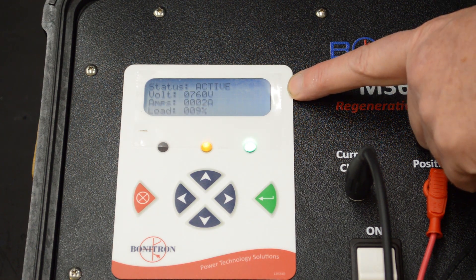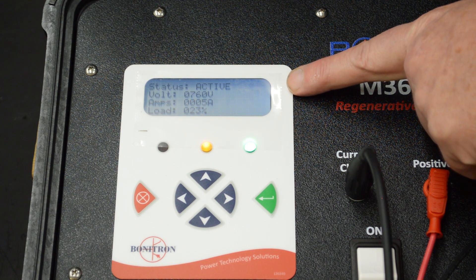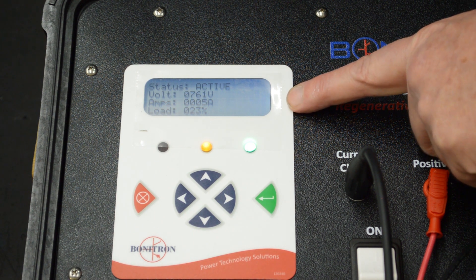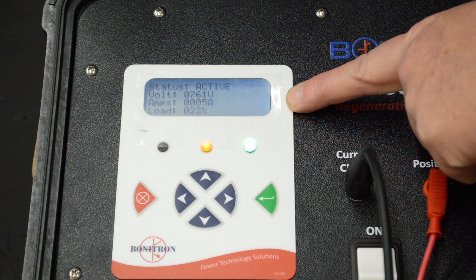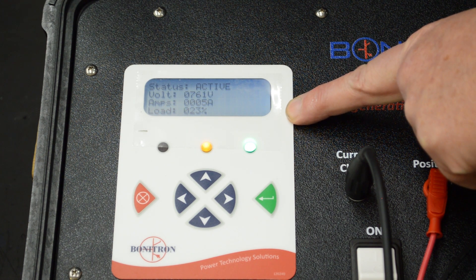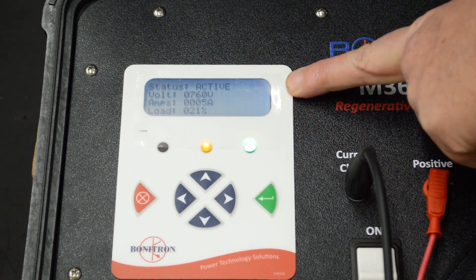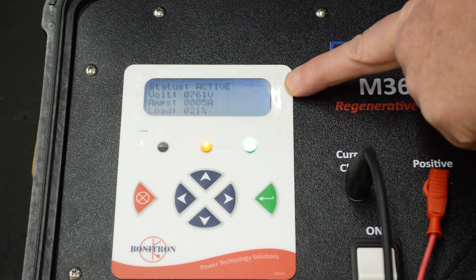As you can see, the parameters of the regen come up right now. We have a 760 volt DC bus, 5 amps, and the load's at 23%. And right now we're doing, we would be braking.